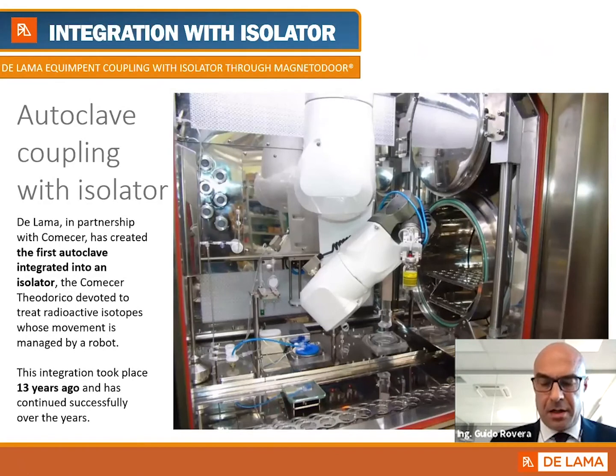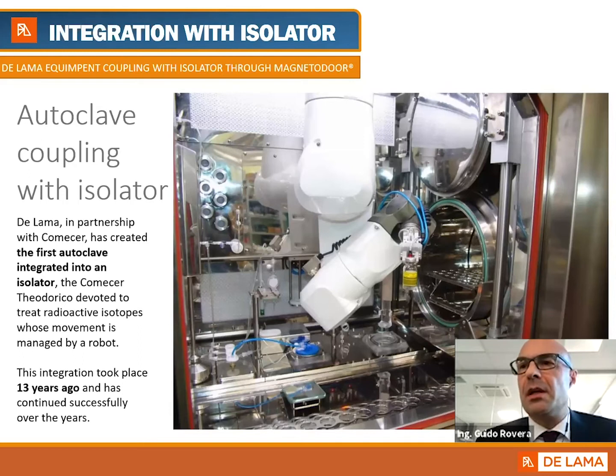Therefore, whatever is the type of process that shall take place in the isolator, we are able to connect it to one of our equipment in order to make it a sort of satellite to the isolator itself. The story began 13 years ago with Comecer, when we first introduced an air steam mixture autoclave into their isolator. It was a unit for radioactive isotopes filling and sterilization. And the unit was specially designed entirely for Comecer.